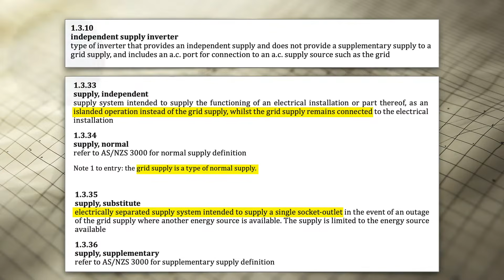Okay, independent supply, what's that about? An independent supply is a supply intended to provide the functionality of an electrical installation, or part of it, as an islanded operation instead of the grid, whilst the grid remains connected. So you can turn off the main switch and still provide power to that independent circuit.